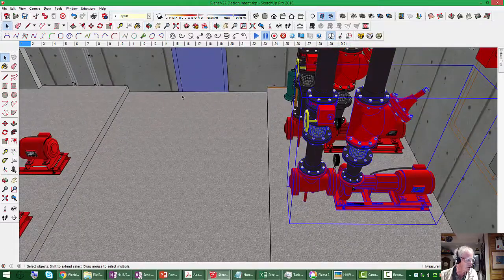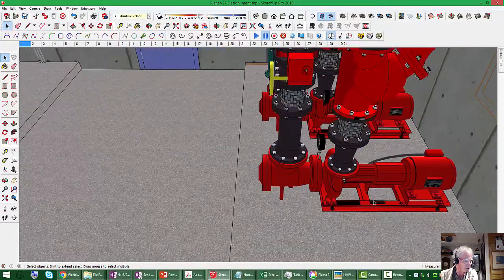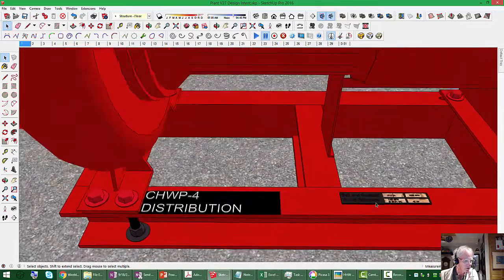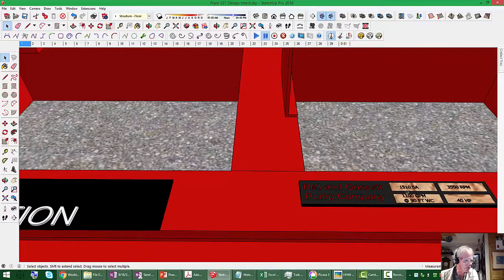remember I mentioned that there's a lot of detail available. You discover that these pumps are identical. We could look at them both, but I'm just going to tell you that. They're identical, and each pump's rated for 1100 GPM. So the question then becomes, is the pipe leaving the plant an 1100 GPM pipe or a 2200 GPM pipe, or how much capacity does the pipe leaving the plant have?